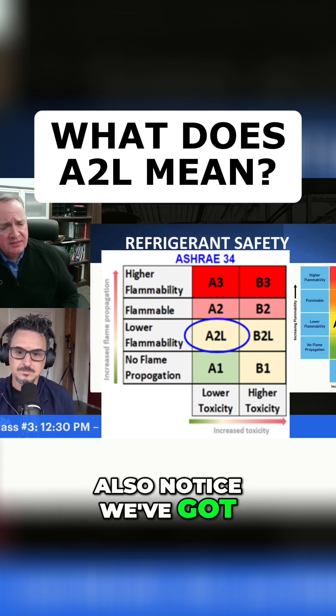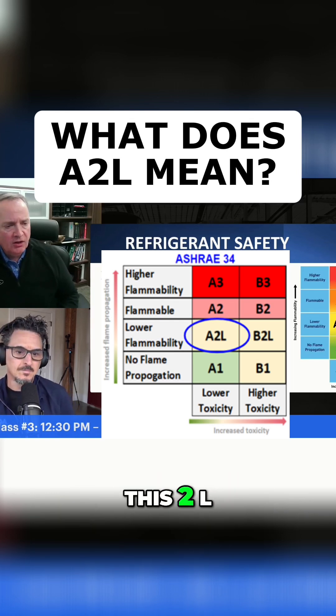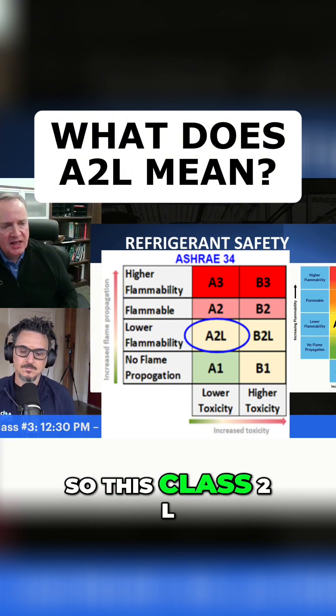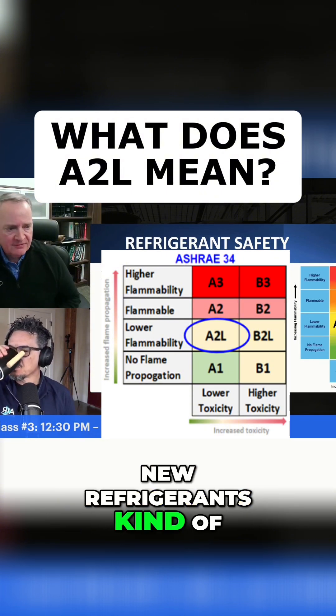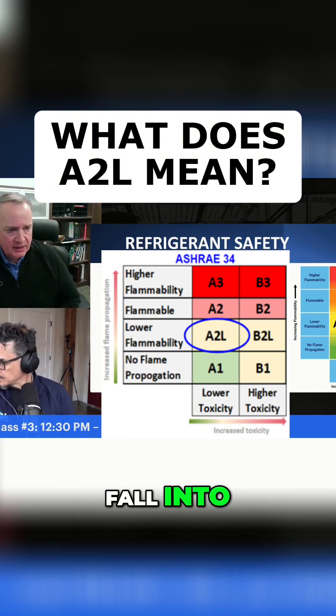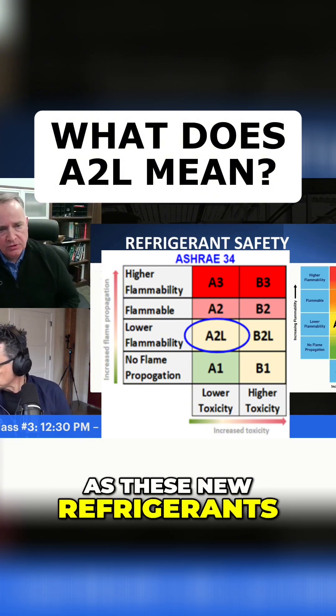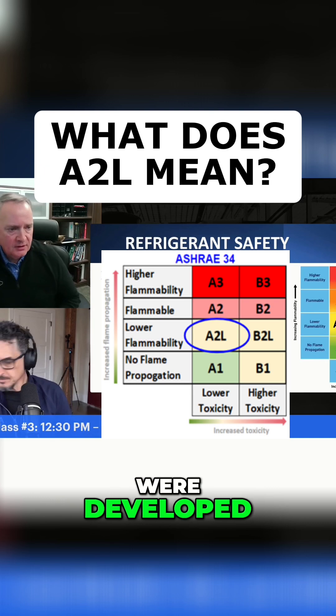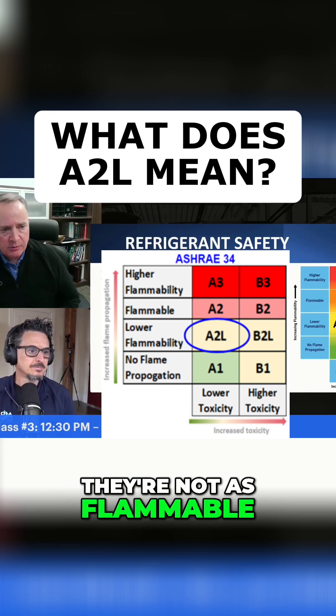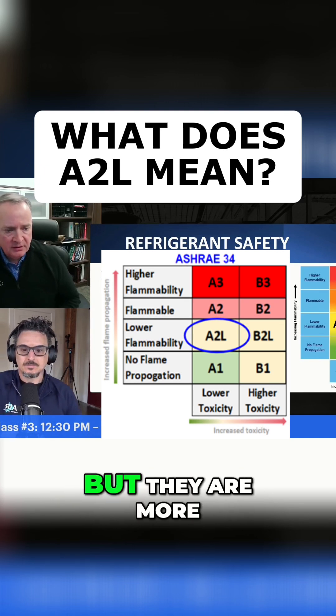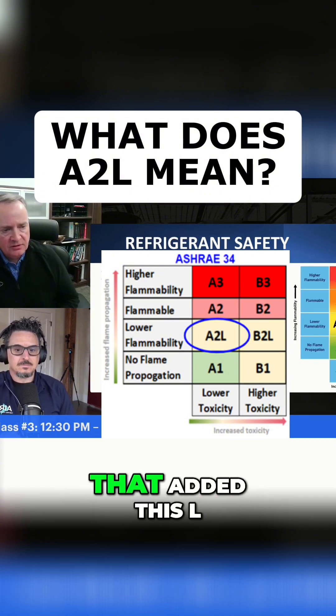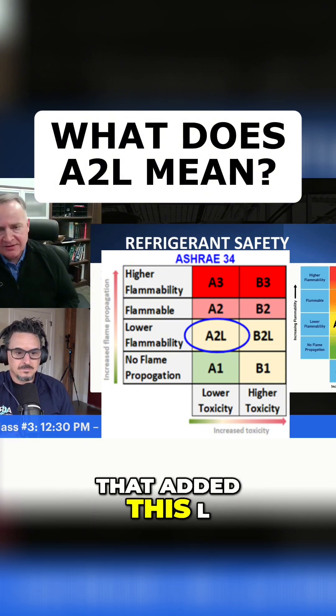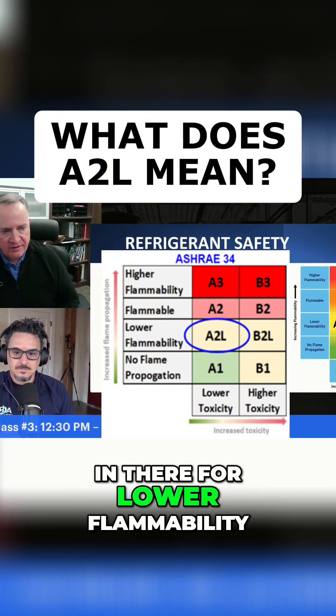You'll also notice there's a 2L class. That's what these new refrigerants fall into. As these new refrigerants were developed, it was realized they're not as flammable as a 2, but they are more flammable than a 1. So they came up with this new category and added the L for lower flammable.